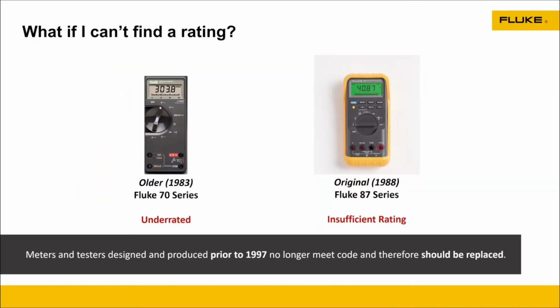Now, the reason why I'm saying all of this is that some meters, you don't find a rating on anymore. Here are two great examples. There are older Fluke 70 series meters, really tried and true. They're underrated. They're actually not rated for some of the voltages at that time. And the mechanics and the electrical components have changed during that era as well. Even the original 1988, the 87 series, has insufficient ratings. Really, any meters prior to 1997 don't meet the code that's out there.